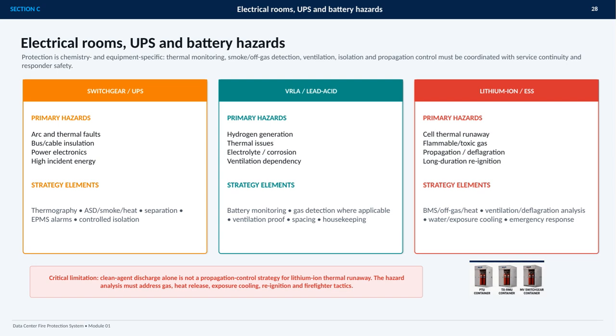For switchgear and UPS systems, the primary concerns are arc and thermal faults, insulation or cable failures, power electronics faults, and potentially high incident energy. The strategy combines thermography, smoke or heat detection, separation, EPMS alarms, and controlled isolation. VRLA and lead-acid batteries introduce different concerns, including hydrogen generation, thermal problems, electrolyte and corrosion issues, and dependence on reliable ventilation. Monitoring, gas detection where applicable, ventilation verification, spacing, and good housekeeping are key controls.